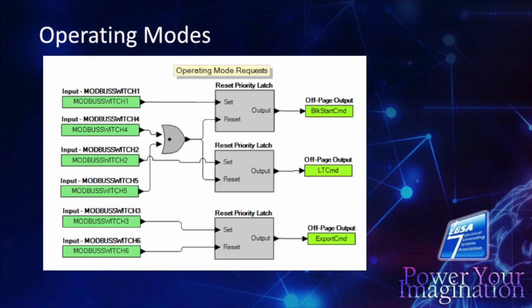So in this case, we can send all of the generator breaker statuses and all the group breaker statuses to the main controller, which is the main utility breaker controller, the one we put the main set of logic in that we're going to use. And we had 3 modes of operation that the customer asked for. The most important one being the black start, because they want a standby generation.